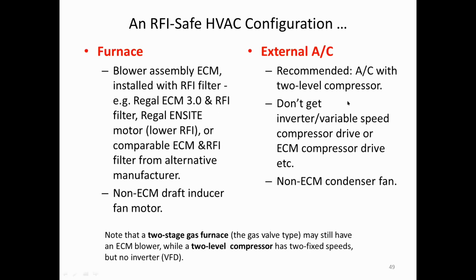For an external AC unit, I would recommend an AC with a 2-level compressor. If you get an inverter with variable speed compressor drive or an ECM compressor drive, if such thing exists, you're likely to have RFI. And I would get a non-ECM condenser fan. Now, in doing so, you're giving up some degree of efficiency. And a 2-level compressor is not going to have the range of, it won't provide continuous coverage of output. It will give you 2 choices of compressor speeds.